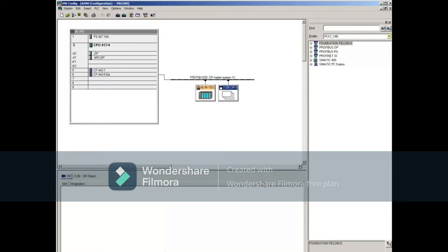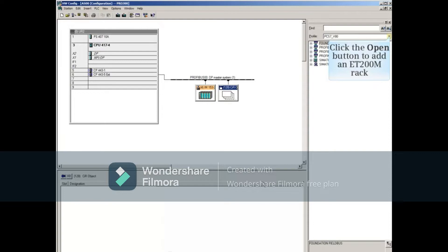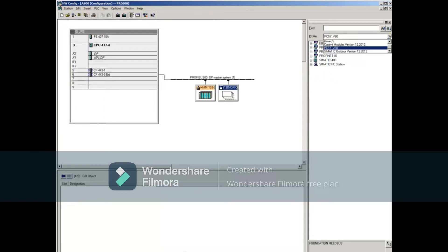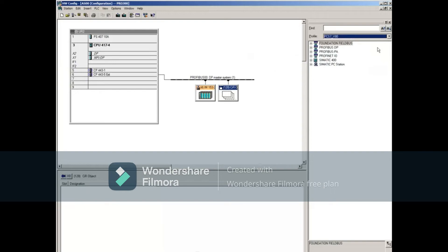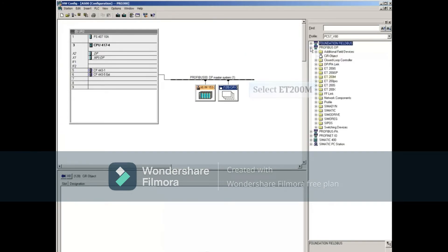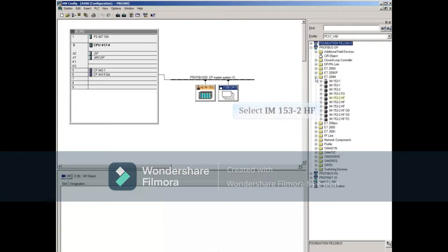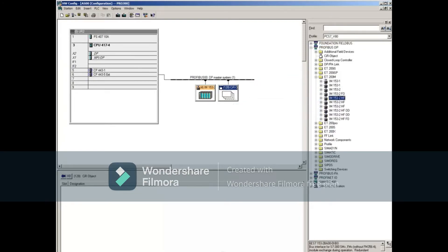Let's add an ET200M rack by selecting the Catalog Profile button on the right. Make sure that the current version is selected. Next, expand the Profibus DP listing, expand the ET200M listing, and select the proper rack. The order number can be verified at the bottom of the catalog.